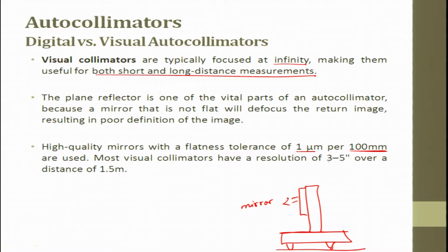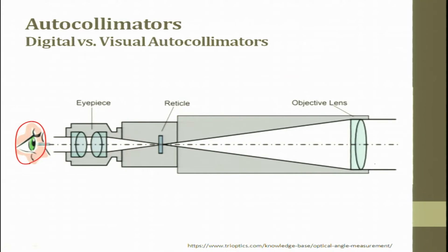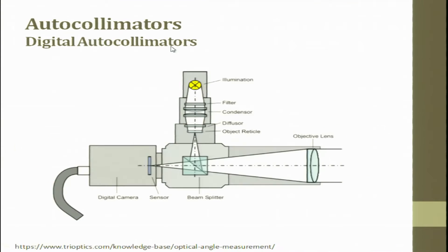Most visual autocollimators have a resolution of 3 to 5 seconds over a distance of 1.5 meters. There is an objective lens, an eyepiece, and reticles. For the digital form, the operator's eye is replaced by a photodiode. In the digital autocollimator, there is an objective lens, then a beam splitter, which goes to an objective with reticles, then a diffuser, condenser, and filters.